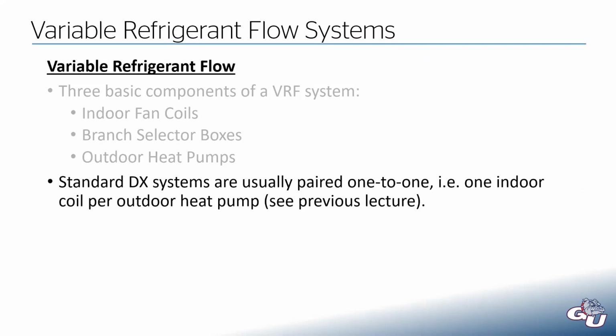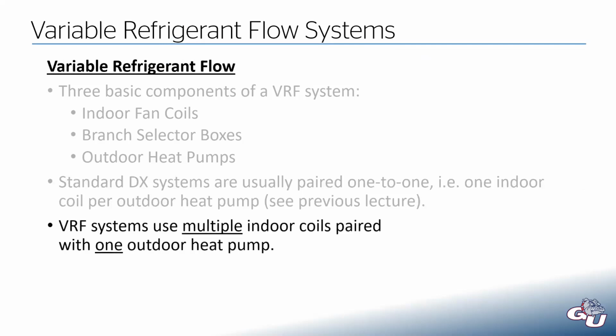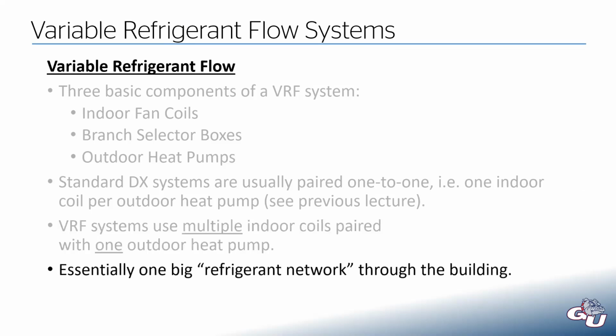A standard DX system, your typical air conditioner, is usually paired 1-to-1, where you have one indoor coil and one outdoor coil at the heat pump, which we talked about in depth last time. So it's usually a 1-to-1 pairing. You have one coil per one outdoor unit. VRF systems, though, have multiple indoor coils that all link up back to one common outdoor heat pump. So you could have 30 to 40 indoor coils that match up to one very large heat pump outside. And this is one big what I call a refrigerant network.